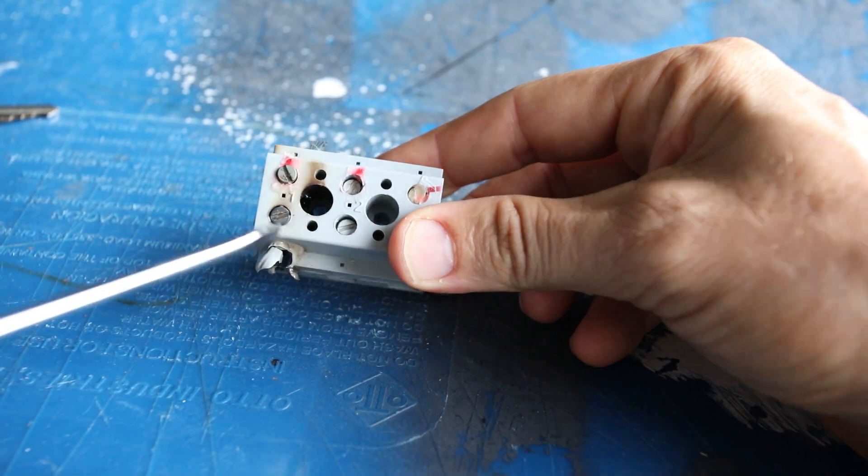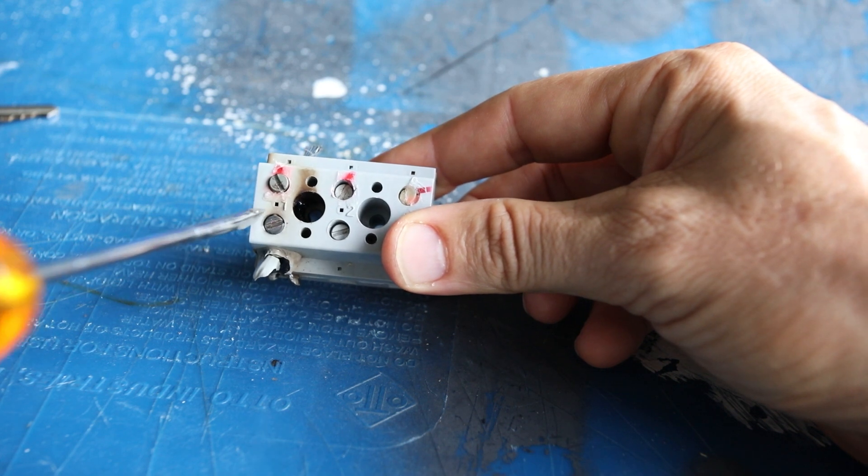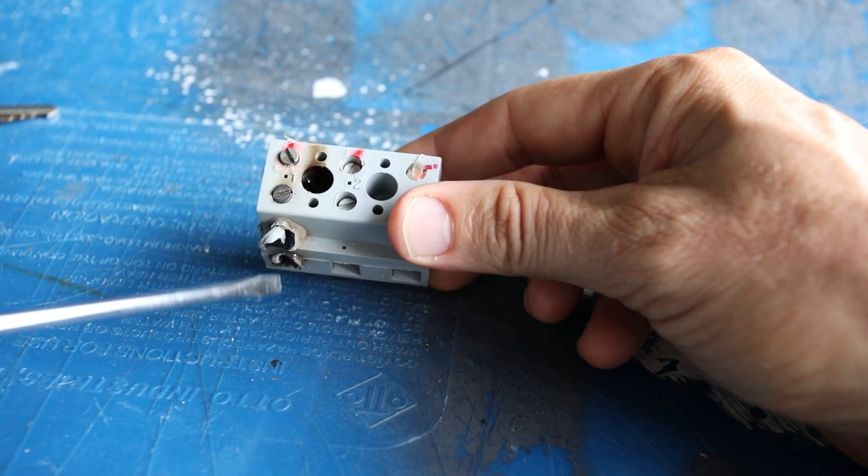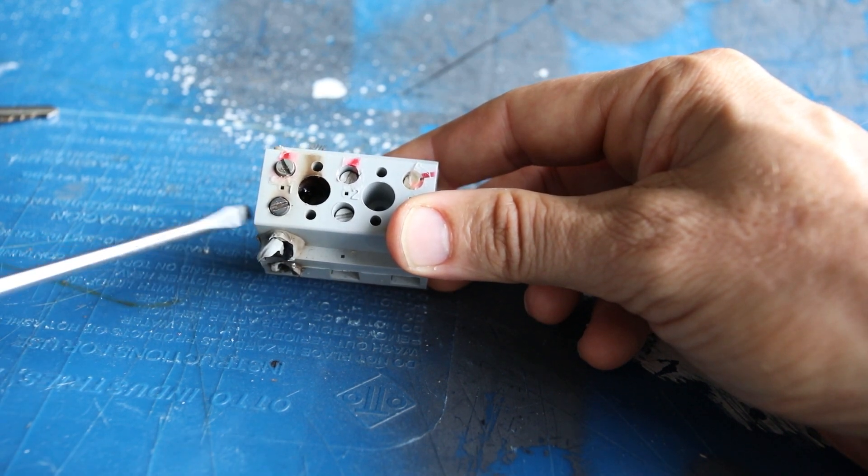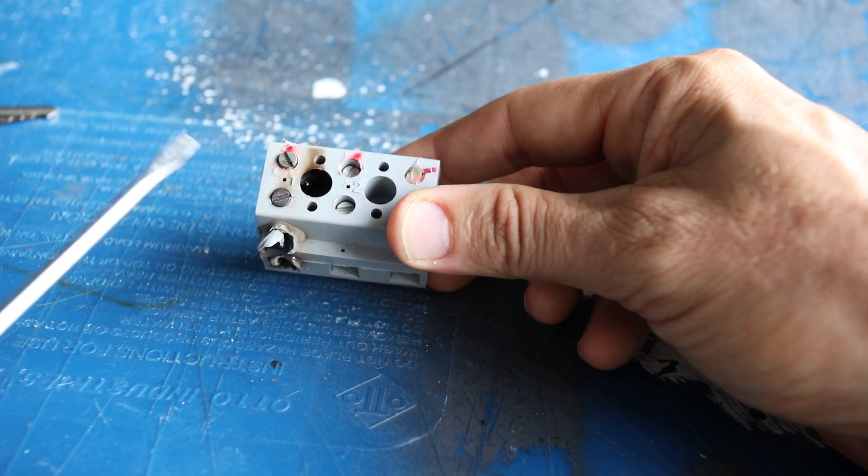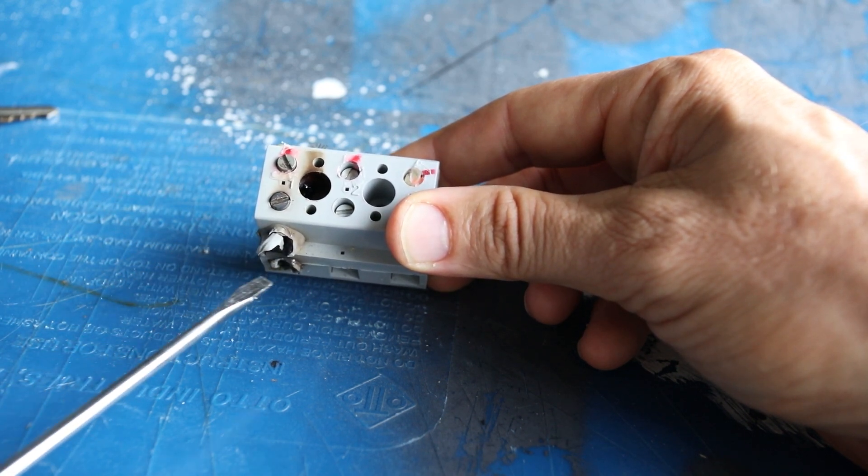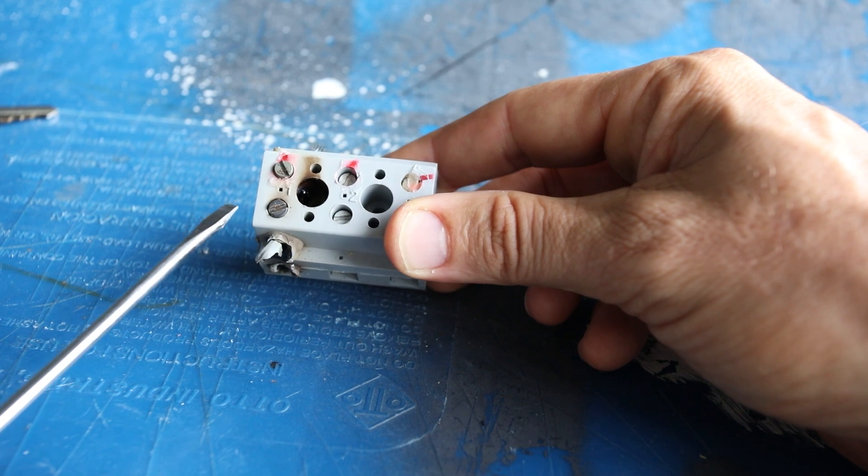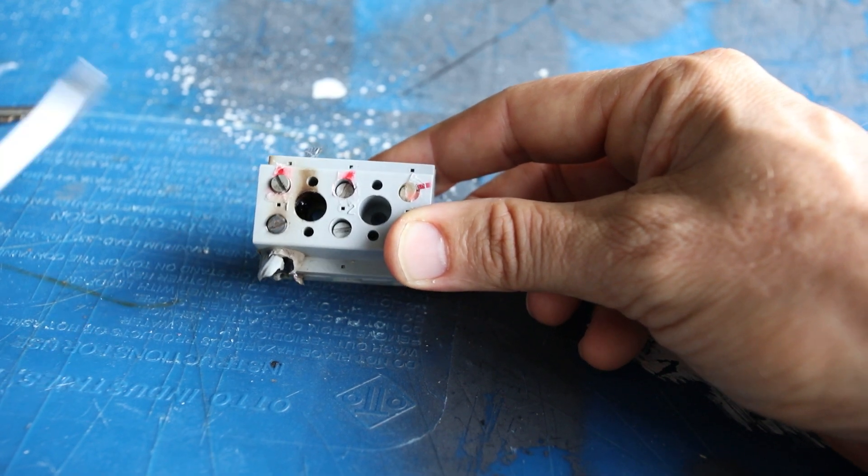What I think happened is with that vibration, this thing's wiggling, this thing kind of just slowly backed itself out and this wire basically got loose. And then that looseness basically caused it to arc and or get really, really hot.